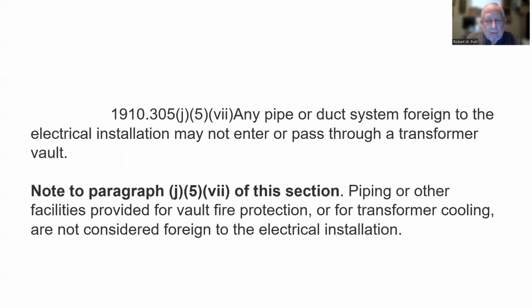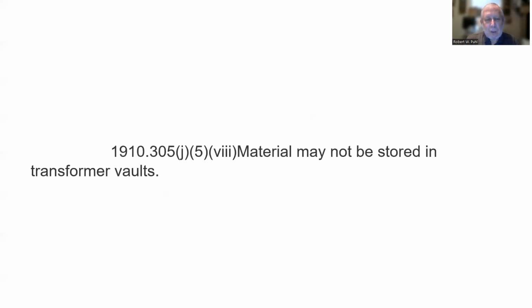Any pipe or duct system foreign to the electrical installation may not enter or pass through a transformer vault. Oh, now here you go. Piping or other facilities provided for vault fire protection or for transformer cooling are not considered foreign to the electrical installation. Well, that makes sense too. Material may not be stored in transformer vaults.